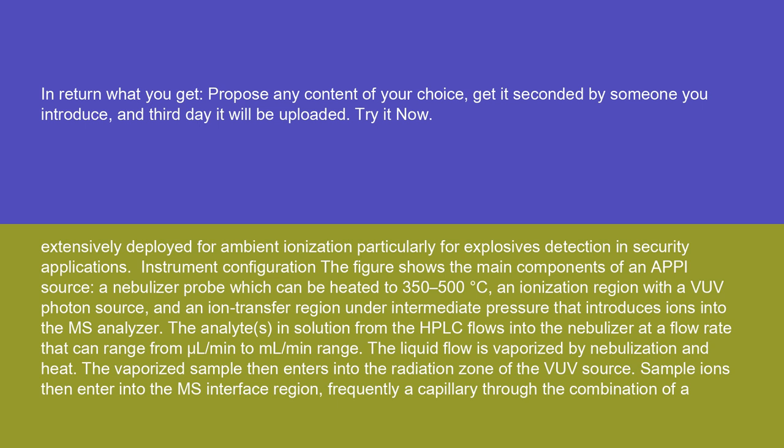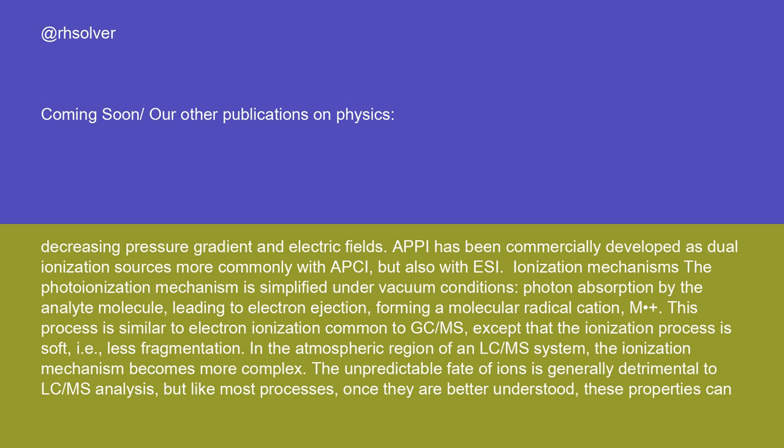Instrument configuration: the figure shows the main components of an APPI source — a nebulizer probe which can be heated to 350 to 500 degrees Celsius, an ionization region with a VUV photon source, and an ion transfer region under intermediate pressure that introduces ions into the MS analyzer. The analyte solution from the HPLC flows into the nebulizer at a flow rate ranging from μL/min to mL/min. The liquid flow is vaporized by nebulization and heat, and the vaporized sample then enters the radiation zone of the VUV source. Sample ions then enter the MS interface region, frequently a capillary, through a decreasing pressure gradient and electric fields. APPI has been commercially developed as dual ionization sources, more commonly with APCI but also with ESI.